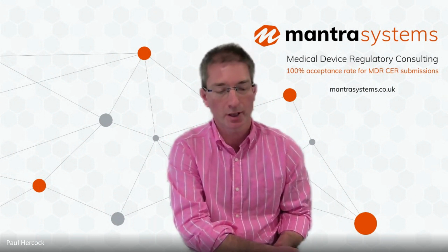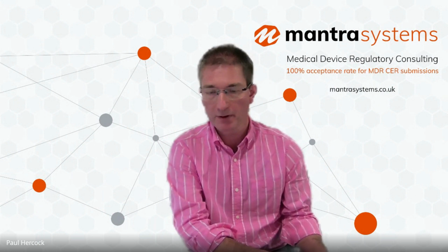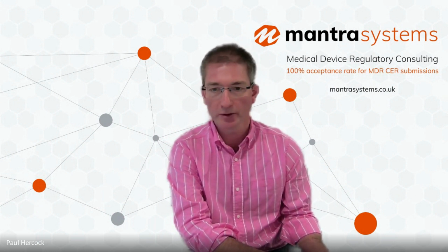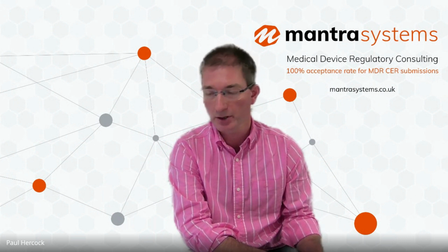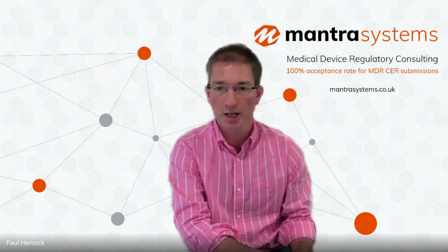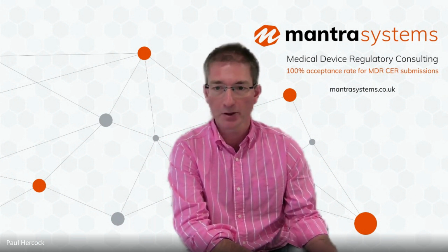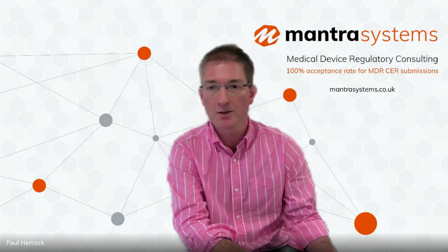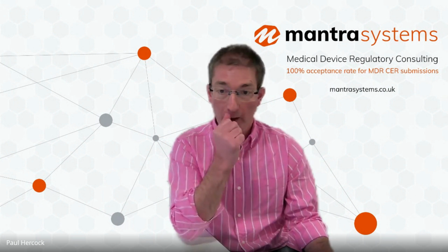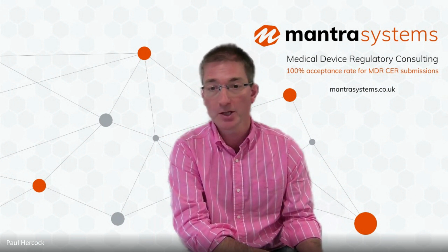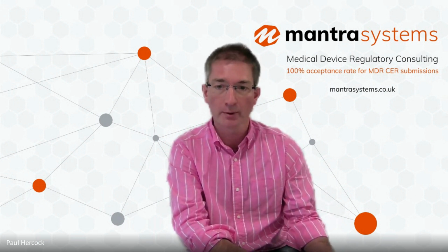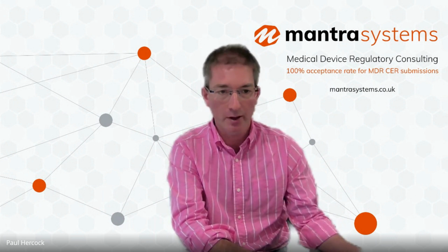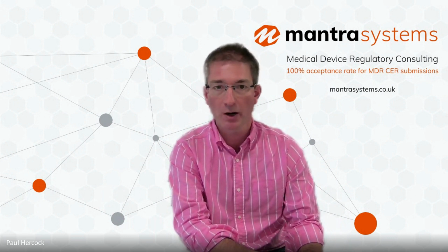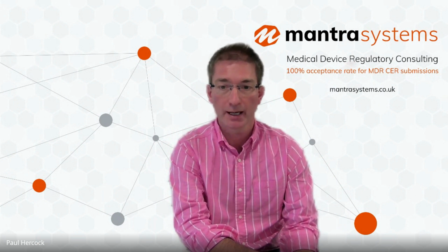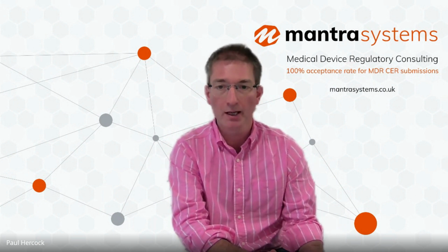The difference, of course, is that with the exception of subtypes of class 1, such as sterile, reusable surgical devices or class 1 devices with a measuring function, a class 1 CER will not need to be submitted to a notified body or an approved body. So you might think, well, why do we need it in the first place? Well, when you sign a declaration of conformity, you're telling the competent authority that you're in alignment with the requirements. And also, as a component of surveillance of the medical device market in their territory, a competent authority may actually request access to the technical files at any time. There's really nothing to gain from not being in alignment with the requirements.